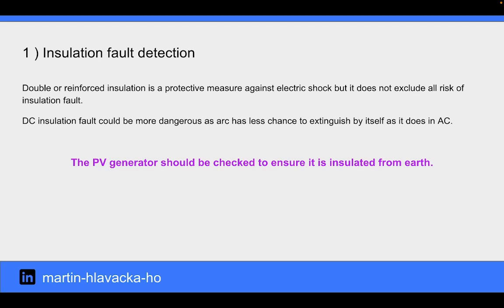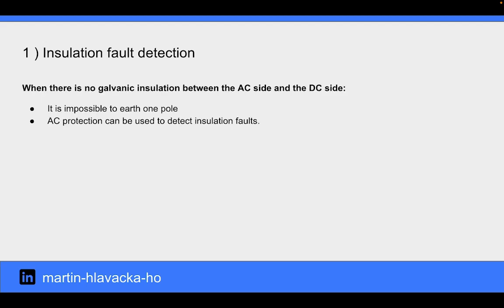Double or reinforced insulation is a protection measure against electric shock, but it does not exclude all risk of insulation fault. DC insulation fault could be more dangerous as arc has less chance to extinguish by itself as it does in AC. The PV generator should be checked to ensure it is insulated from earth. When there is no galvanic insulation between the AC side and the DC side, it is impossible to earth one pole. AC protection can be used to detect insulation faults.